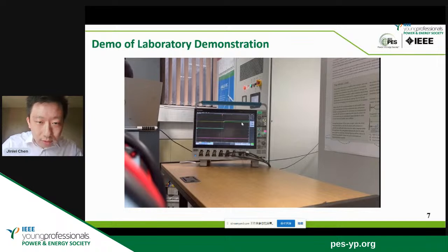Then we could enable the DC voltage control to make the DC voltage reach the given reference. I use the ramp function to slowly increase the DC voltage to the reference. After the DC voltage is stabilized, the power control can be enabled afterwards. The right curves indicate the AC current.